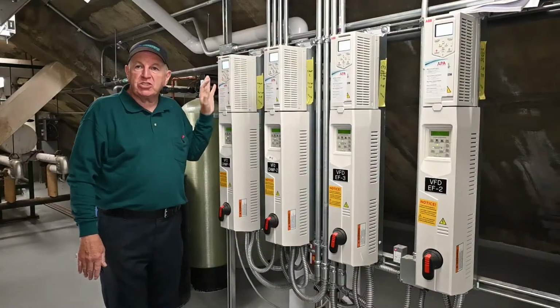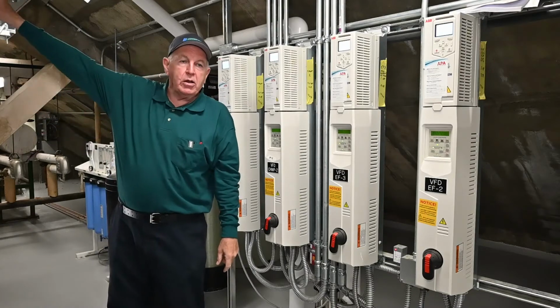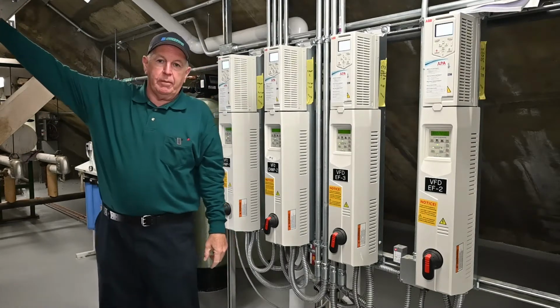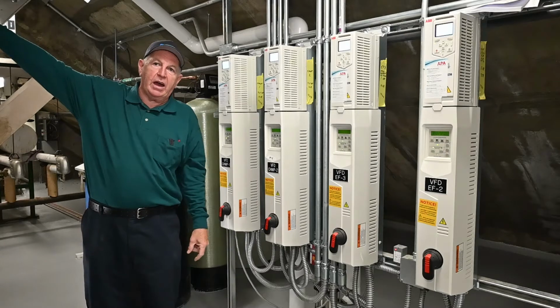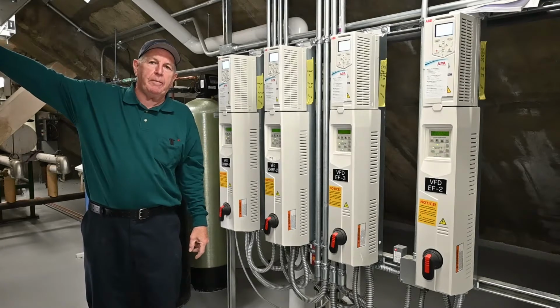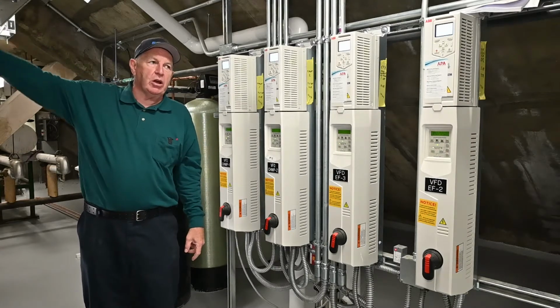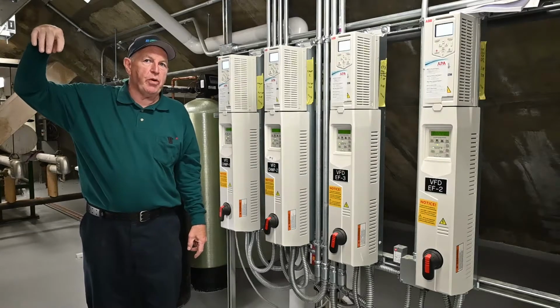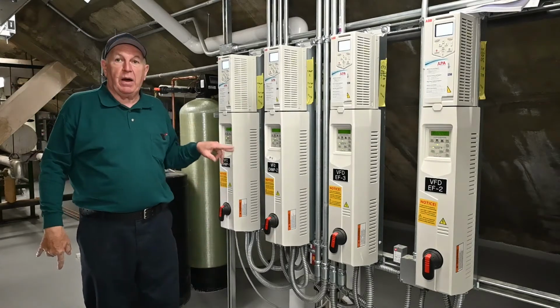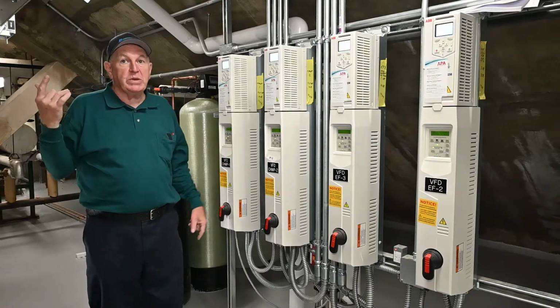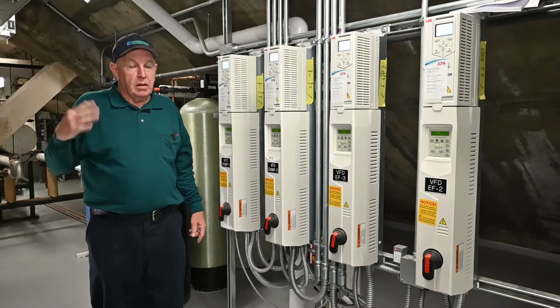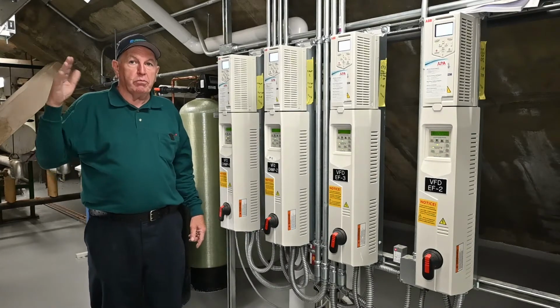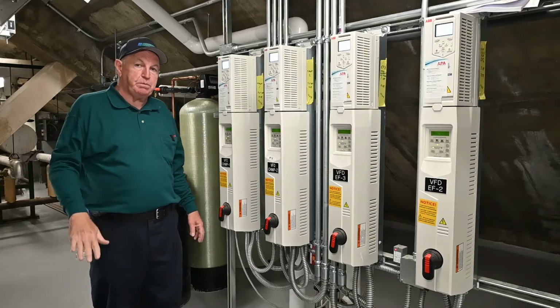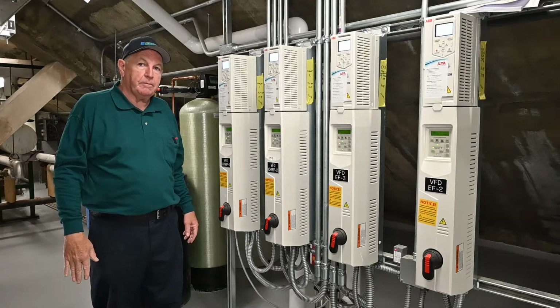The differential pressure sensor is on the glycol piping, two thirds of the way down, just before the pipes go up to the chiller. There's two taps with a differential pressure transducer that runs these pumps. So when the valve opens in the air handler, the pump will speed up, or as the valve shuts, the pump will ramp down. And that's about it.